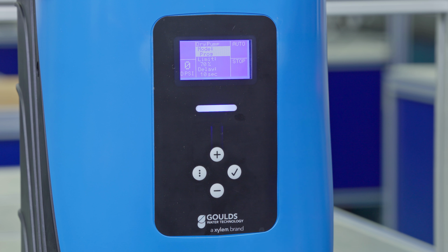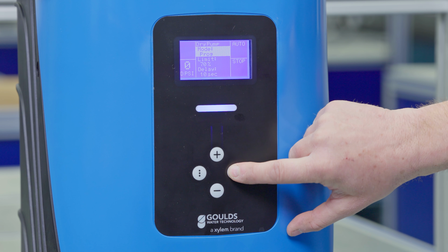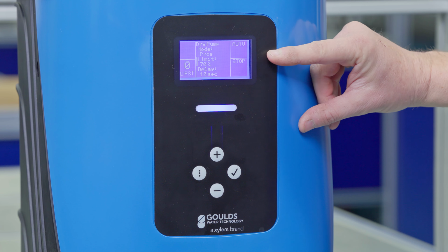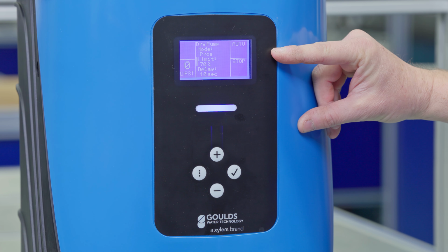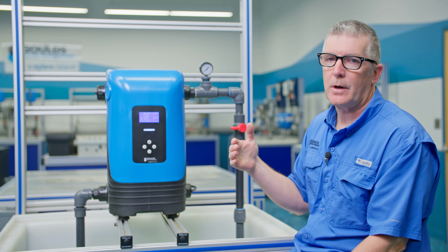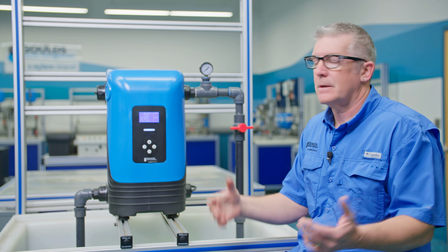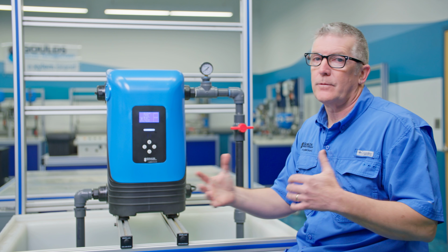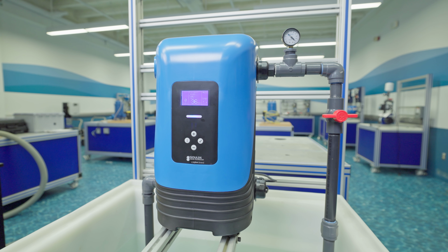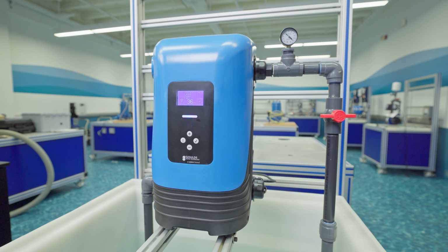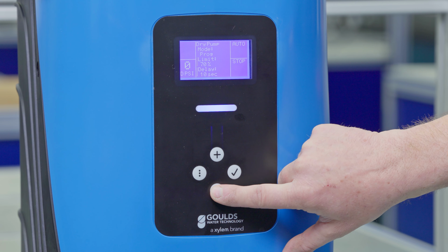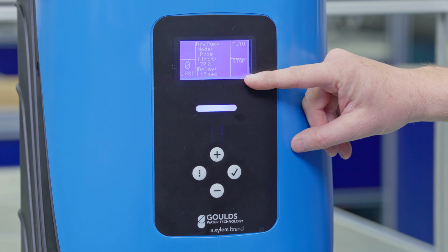So let's leave that at progressive. So again, I'm going to save that. I'm going to go down. So again, more on dry pump. This is a limit. This is a percentage of the amperage of the pump, so you could change that. If it's too sensitive or not sensitive enough, you could change that percentage of, again, the motor amperage. So we're going to leave that at 70%. And the next one here is the delay.